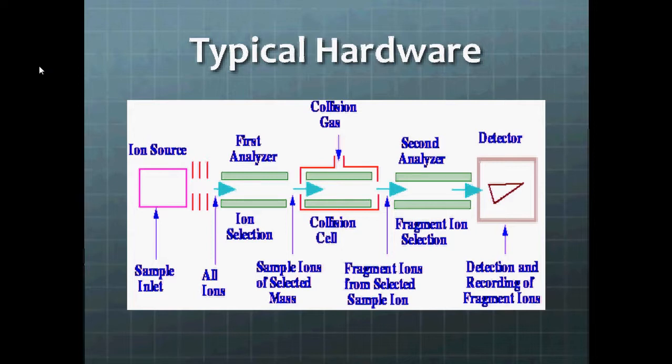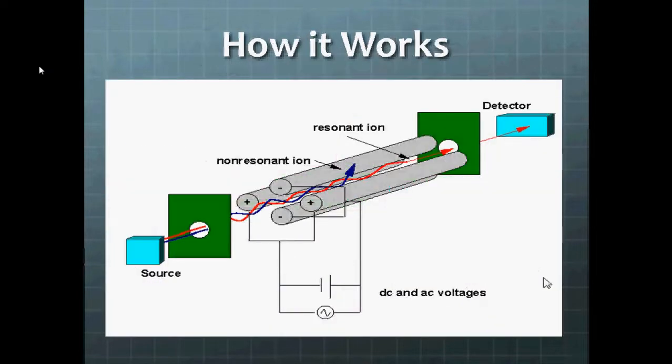And then those that make it through will enter the second quadrupole or the collision cell, where the ions will collide with collision gas and fragment further. Those fragments will be accelerated through the third quadrupole where they'll be filtered again according to mass to charge ratio until they reach the detector, which is usually an electron multiplier.